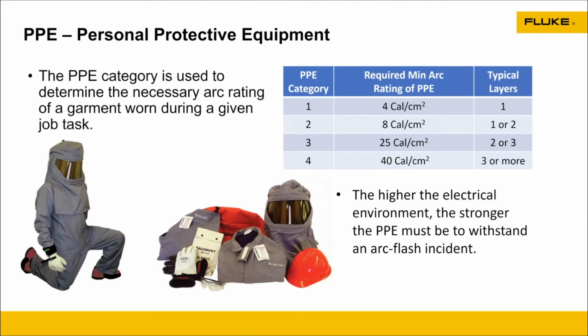They sell category Cal 4 shirts all over the place. Where we get into higher voltages and higher currents and that potential energy, you might need a category 4 rated outfit. Now, this is where you look like Darth Vader. You're fully covered, you've got your arc flash gear. So knowing what your potential is and where you're working would really determine that PPE.